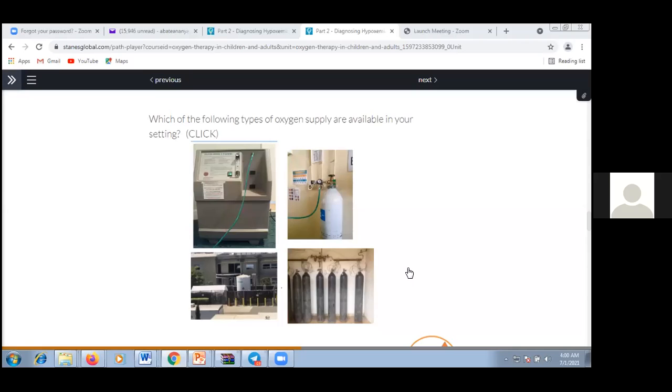In case all the cylinders run out of oxygen, then we were faced with the whole ICU, all the ICU beds, running out of oxygen at the same time. So this was one of the big downsides we saw in that system.